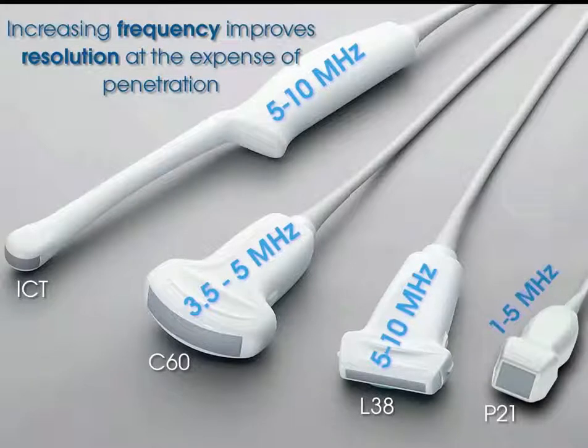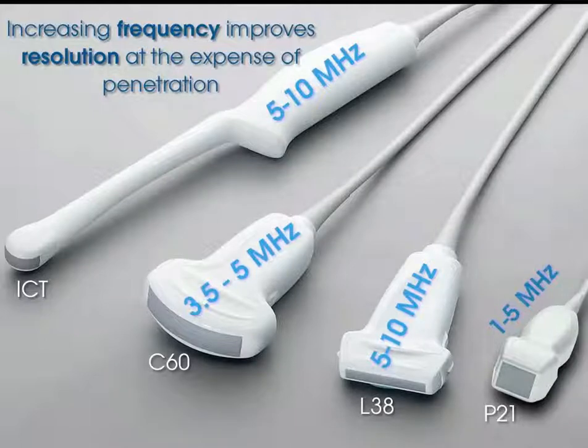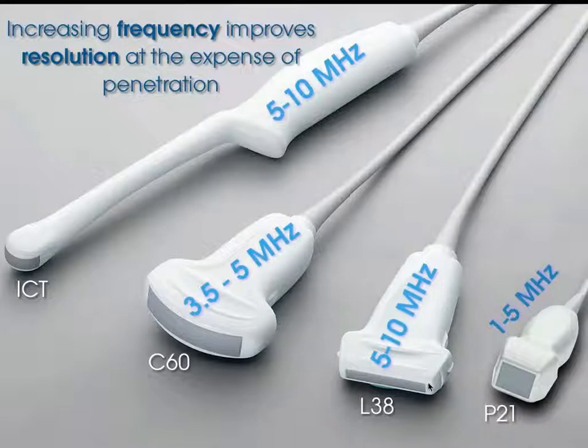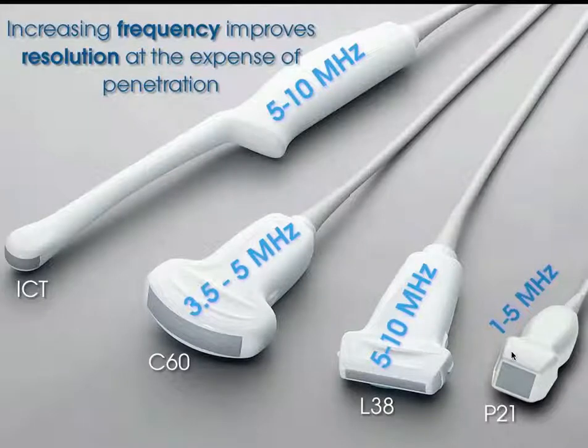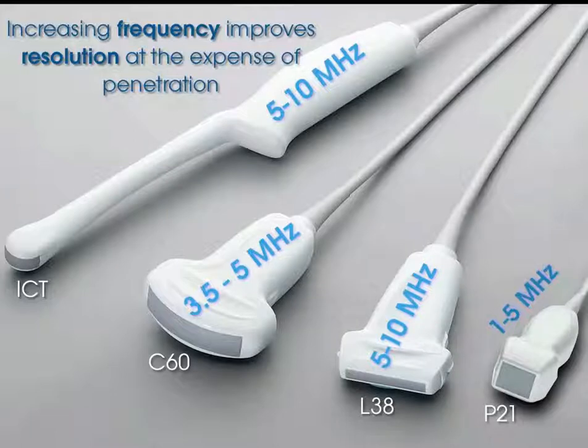Transducers themselves have different frequencies they can toggle between. Generally, higher frequency transducers have better resolution but cannot penetrate as far into the body. A high frequency linear transducer is good for superficial structures when depth of penetration is not a concern, whereas a lower frequency transducer is good for penetrating deeper into body tissues. You always want to use the highest possible frequency that will get you to the depth of interest.